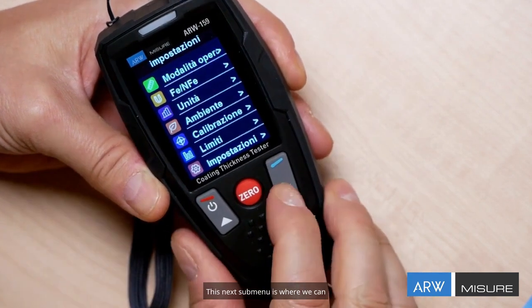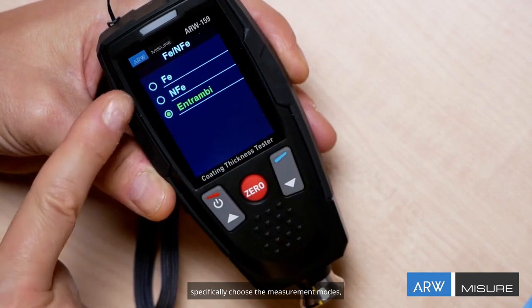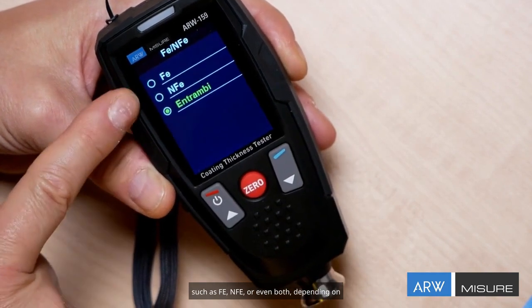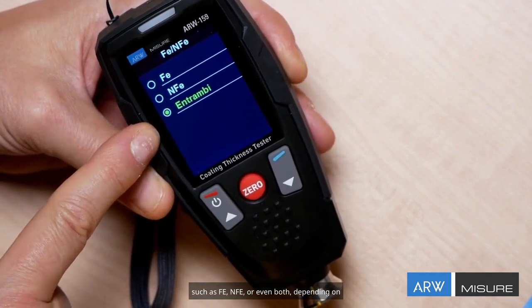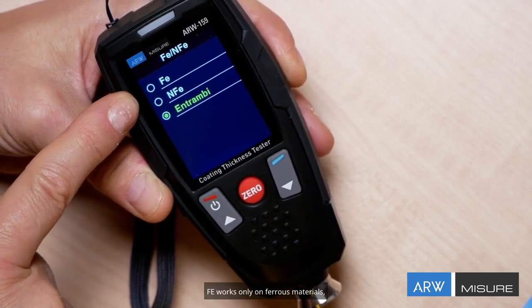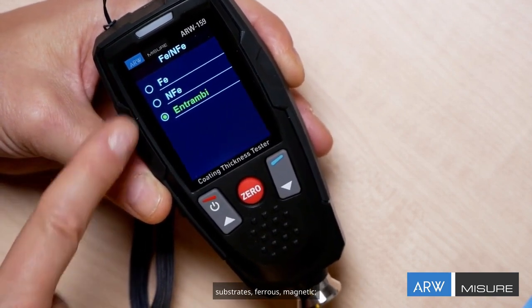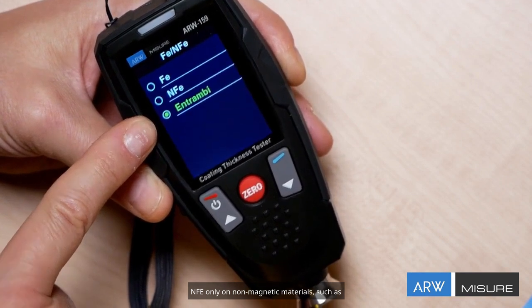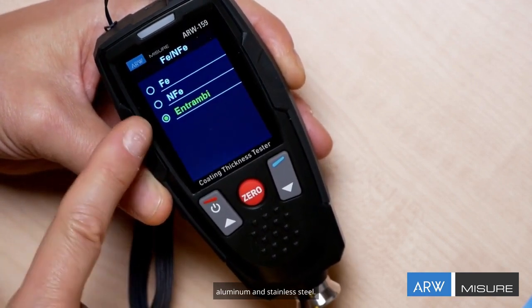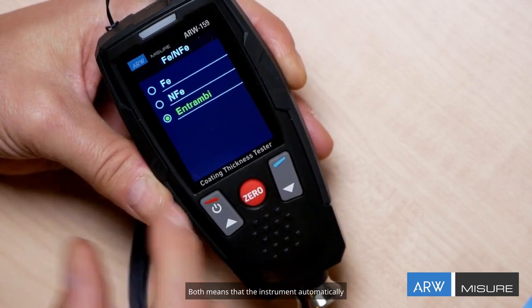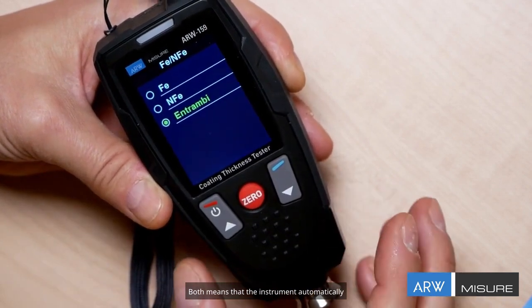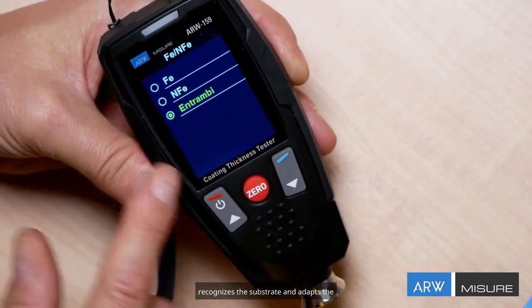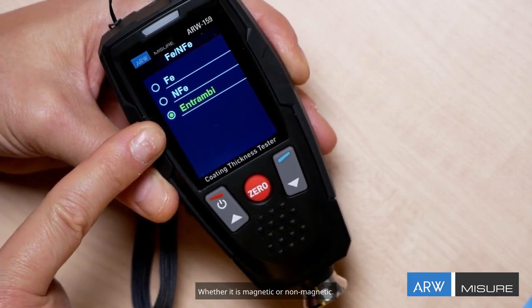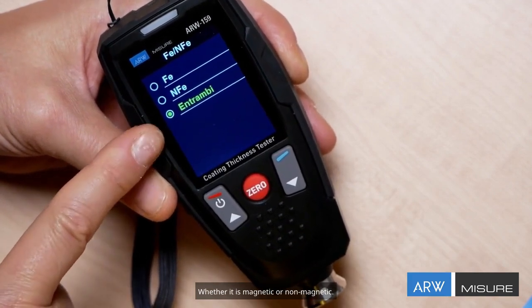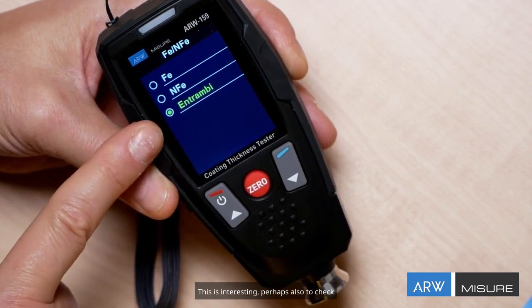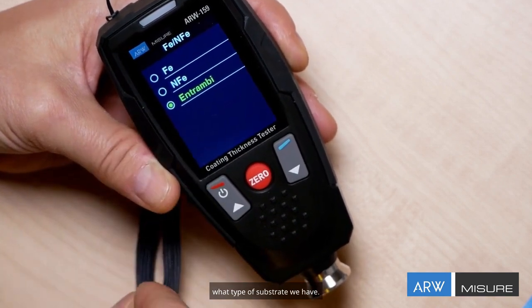This next submenu is where we can specifically choose the measurement modes, such as FE, NFE, or even both, depending on your needs. FE works only on ferrous materials, substrates, ferrous-magnetic, NFE only on non-magnetic materials such as aluminum and stainless steel. Both means that the instrument automatically recognizes the substrate and adapts the measurement depending on whether it is magnetic or non-magnetic. This is interesting perhaps also to check what type of substrate we have.